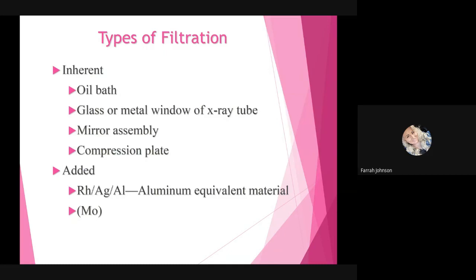So, types of filtration. Inherent filtration, meaning within the tube, you're going to have your oil bath, which surrounds your X-ray tube. You're going to have the glass or metal window of your X-ray tube that is going to absorb low energy photons. You also have your mirror assembly, and then of course the compression plate. Examples of added filtration are going to be rhodium, silver, or aluminum equivalent material, and typically those are used to determine what the half value layer is. And then also molybdenum can be an example of added filtration.